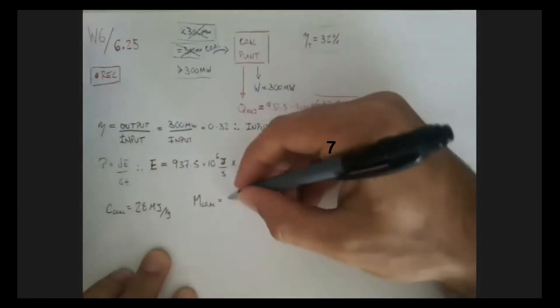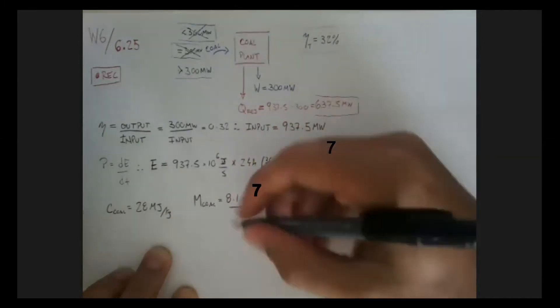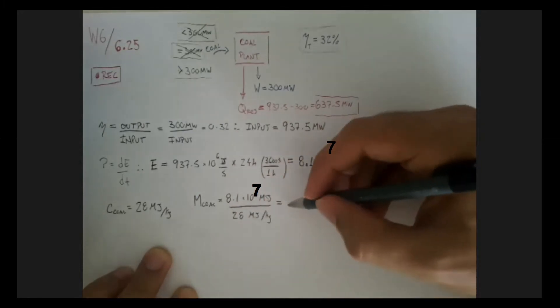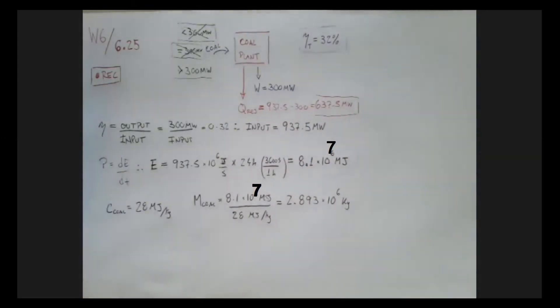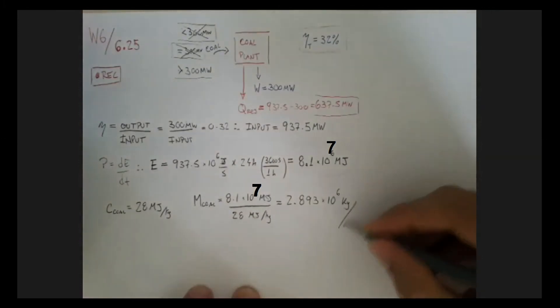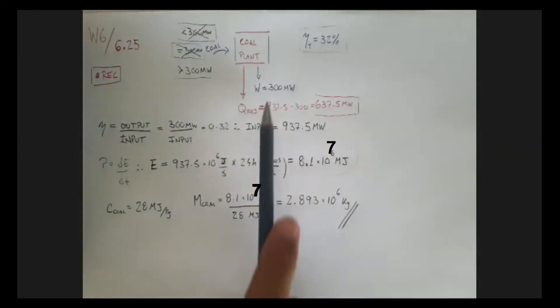Mass of coal will be the 8.1 times 10 to the 7 megajoules divided by 28 megajoules per kilogram. I'm going to have my answer in kilograms. And this is about 2.893 times 10 to the 6 kilograms. So this is, according to our calculations, the amount of coal I need to put into this plant over a 24-hour period, so that this plant can generate energy at a rate of 300 megawatts. That's part A of our problem.